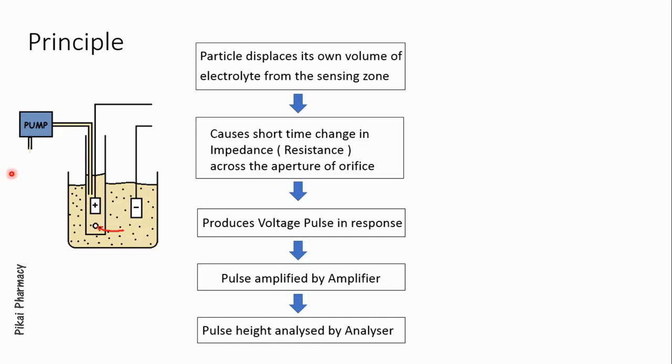This instrument counts the number of particles suspended in a solution and also determines their size. There is a pump attached to the glass tube which pumps a known amount of electrolyte from the outer solution. A fixed volume of electrolyte moves from the outer solution to the inside of the glass tube through that tiny orifice, and during this movement the suspended particles also enter through the orifice.